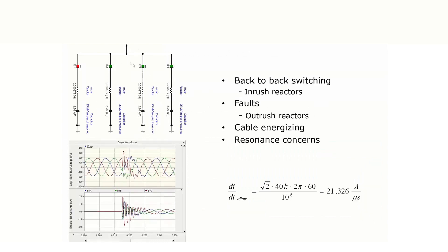For capacitor bank switching, the large inrush current drawn at the beginning is the main concern. Standards have limited this magnitude — for example, a general purpose breaker has a maximum current of 15 kilo-amperes, and the oscillation frequency cannot exceed 4.2 kilohertz. You want to ensure through your simulations that the inrush current does not breach these standard requirements.